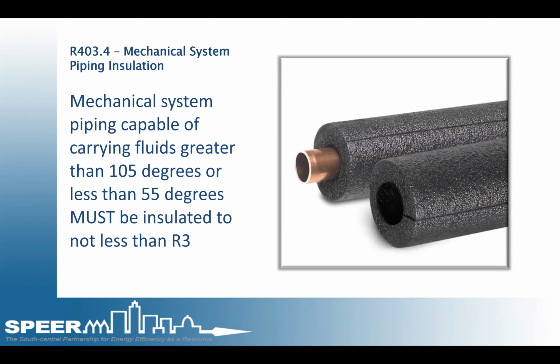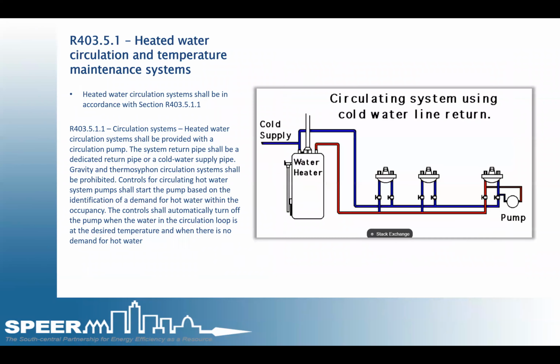R403.4, mechanical system piping insulation. These include, but not limited to, hot water piping, the large refrigerant line for HVAC units, and the condensation piping from the main condensate line for the HVAC unit. So a lot of times the condensation pipe is overlooked. So any joints and connections within this insulation should be taped to avoid any future separation.